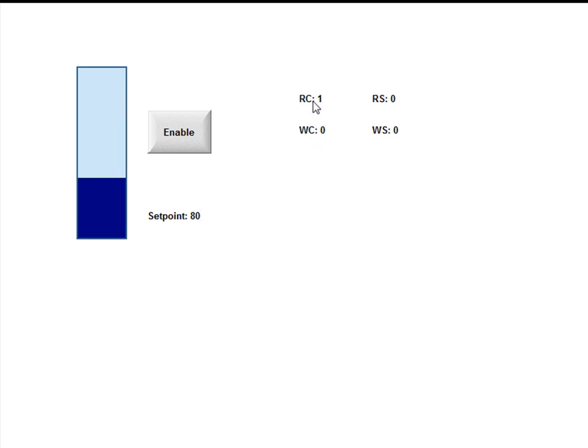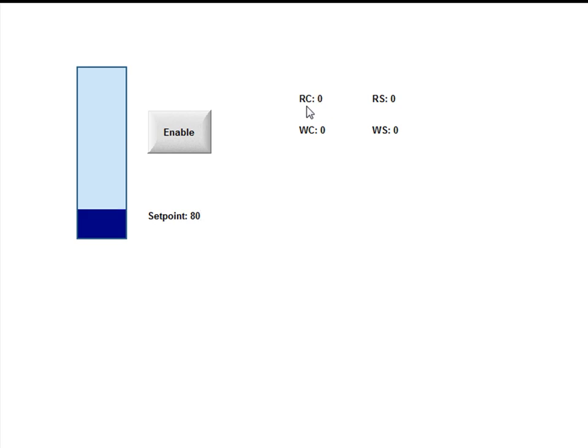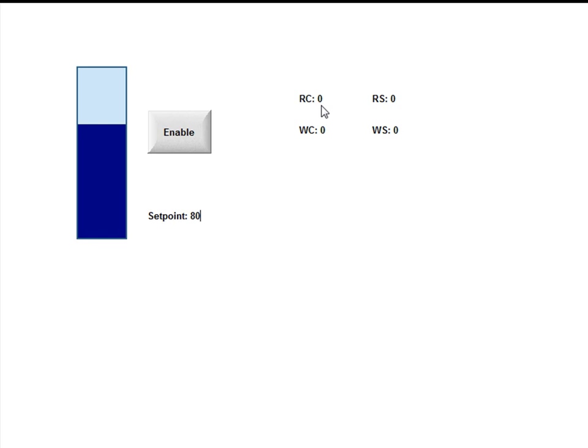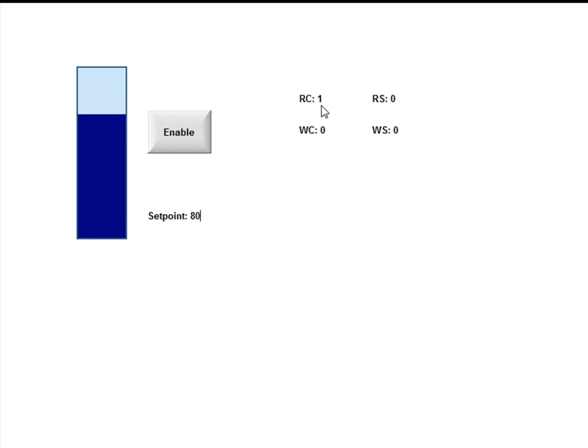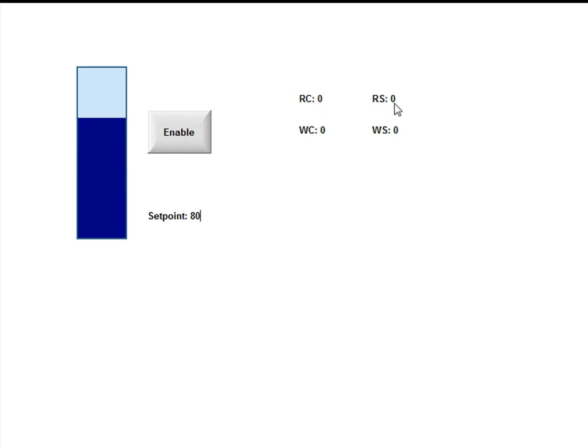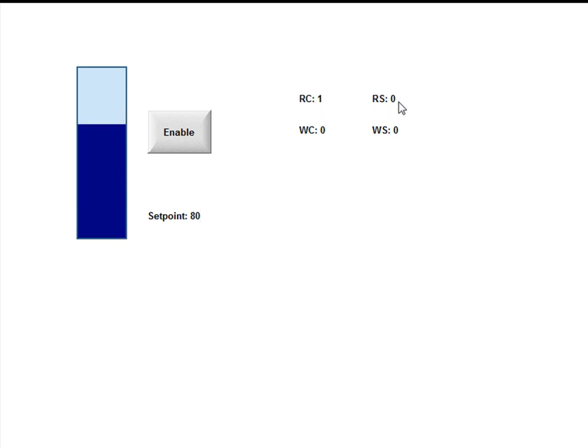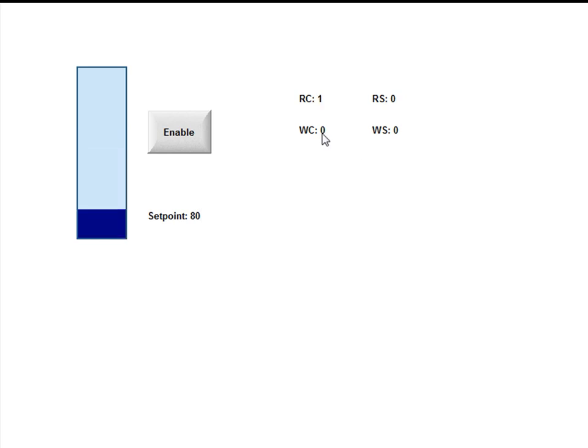Now, what we have going on here with status is I have read complete toggling between 0 and 1 every time it does a read. In this case, when I use the main driver sheet, it's about every 600 milliseconds or so. The read status is 0, which is a good status, means there's no error codes.